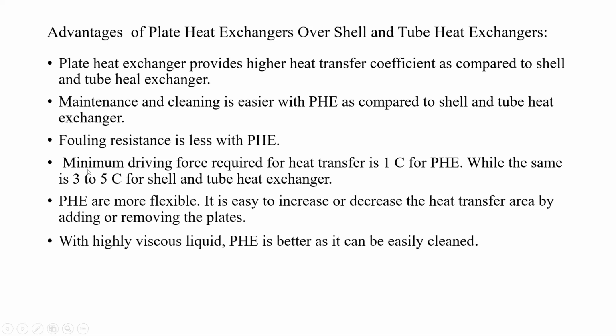The minimum driving force required for heat transfer is 1 degree centigrade for a PHE, while it is 3 to 5 degrees centigrade for a shell and tube heat exchanger. Now, PHE is more flexible. Why is it more flexible? Because we can increase or decrease the heat transfer area by adding or removing plates.